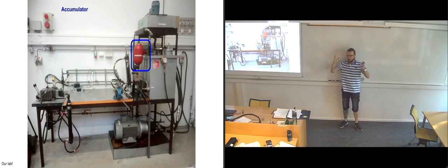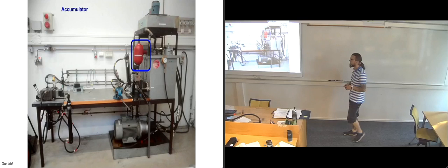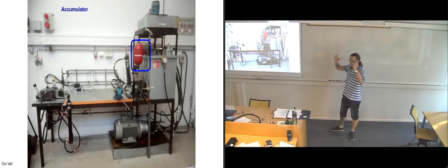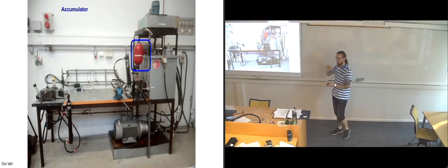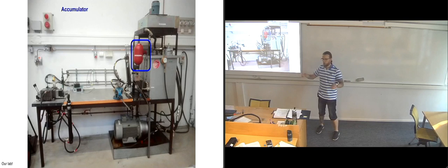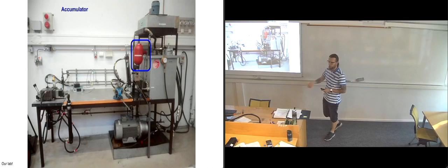And the balloon isn't really big to begin with, so when you've filled it up, it's going to want to push back into its original state. So that when you've filled it up, you can later on release the fluid that's inside the accumulator.